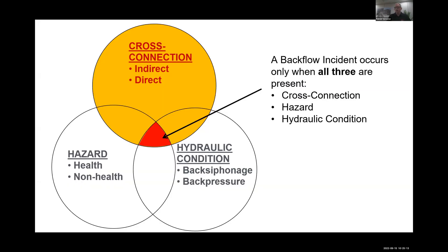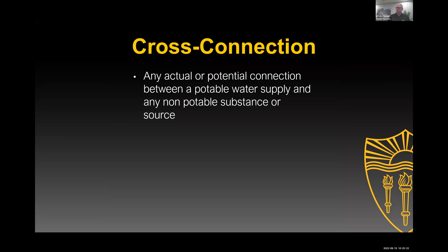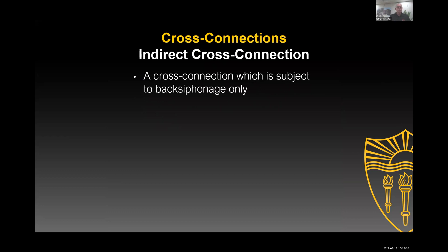Back pressure or back siphonage requires a cross connection — a physical connection. It's a direct or indirect connection: an actual or potential connection between potable water and any non-potable substance or source. If it's indirect, it's subject to back siphonage only. If it's direct, it's subject to back pressure or back siphonage. For example, a recirculating fountain: the pump continually recirculates. If the makeup line goes into piping under sufficient pressure, that could create back pressure. If the line just goes over the lip and drops into the reservoir, then only back siphonage could occur — you'd need sub-atmospheric pressure to suck the water up over the rim and into the drinking water supply.